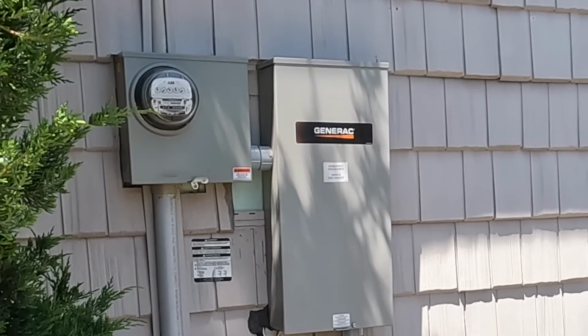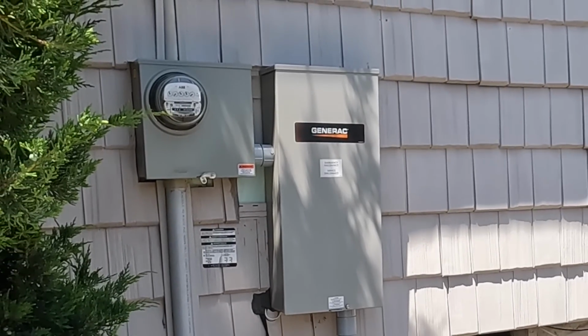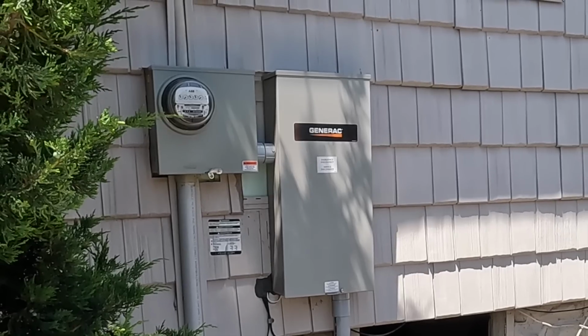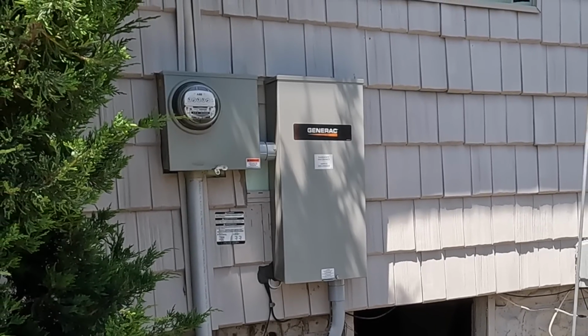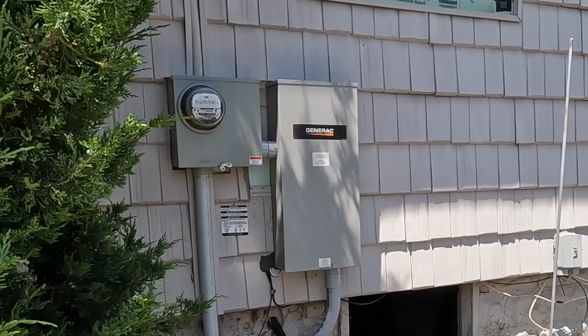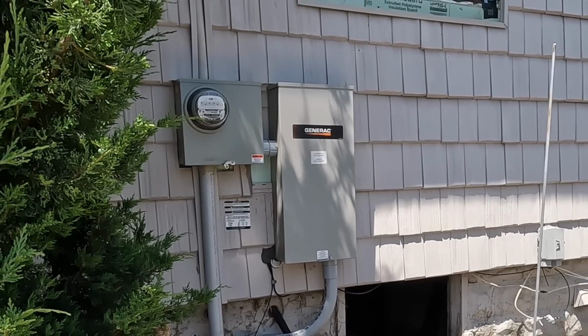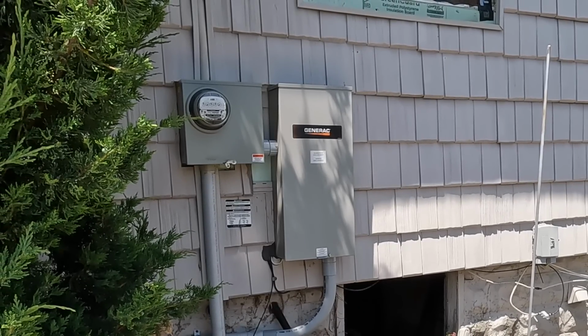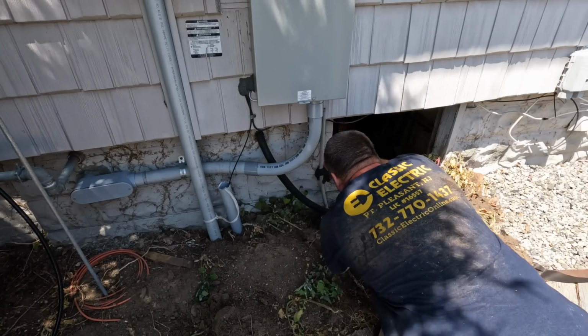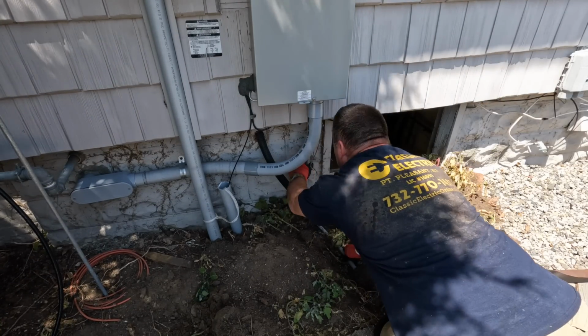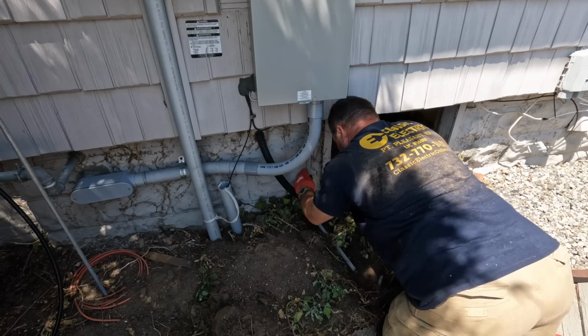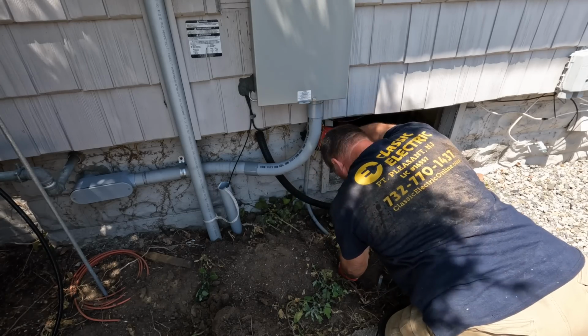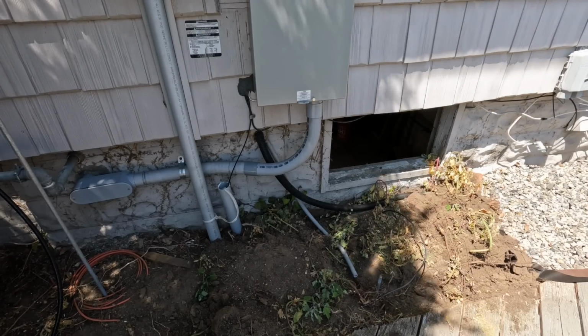Okay, so here's the 200 amp service with the automatic transfer switch. Like I said earlier in the video, I did not record this work when I did it, but obviously it's a 200 amp meter we put in. It's a 200 amp automatic transfer switch. It's service rated, and I'm here today updating the grounding electrodes, which is 2 ground rods and of course the copper water pipe in the basement.